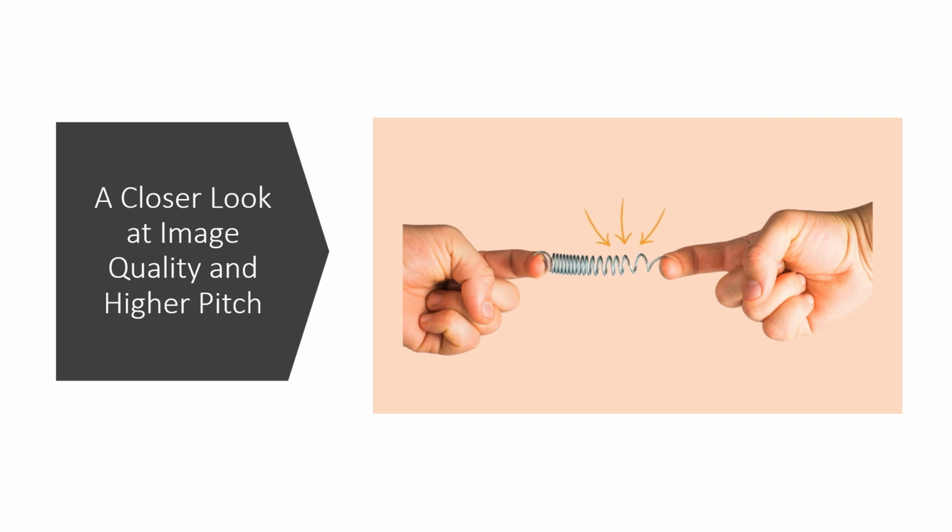Additional interpolation is needed to straighten the slant and maintain image quality. However, if too much interpolation is used, it can result in a reduction of image quality and introduce artifacts such as blooming of the effective slice thickness.